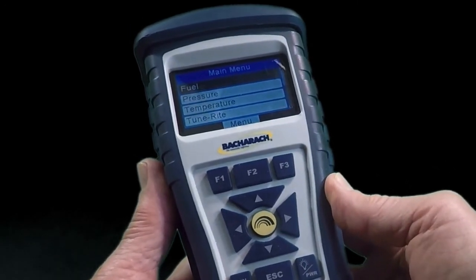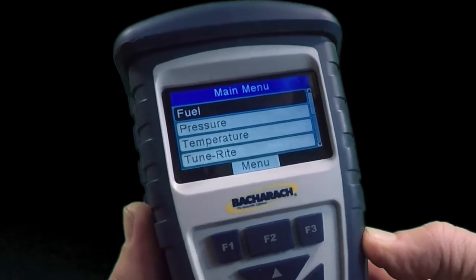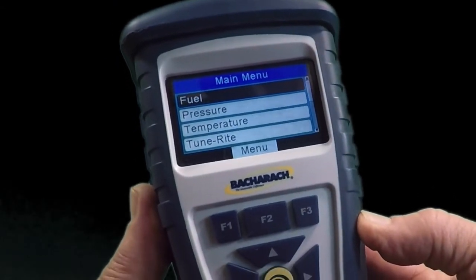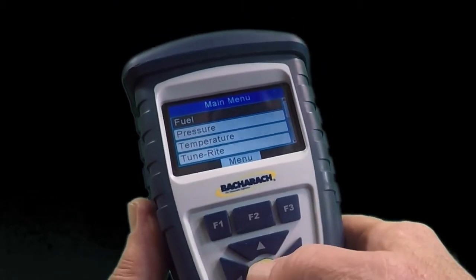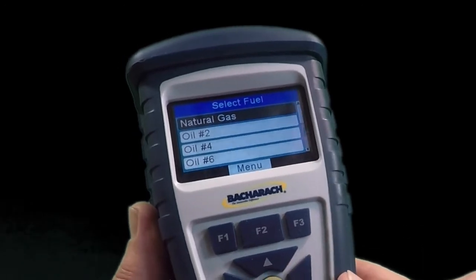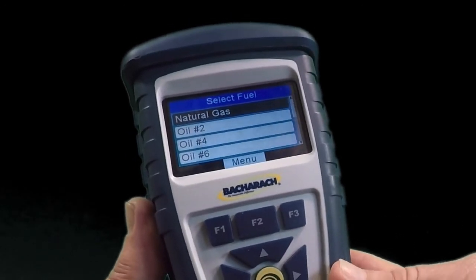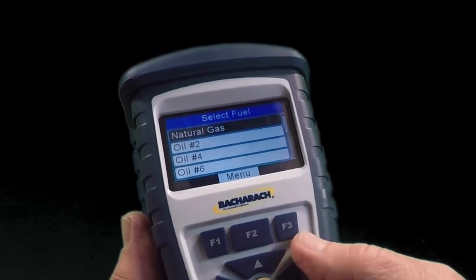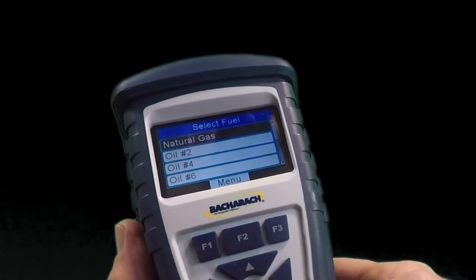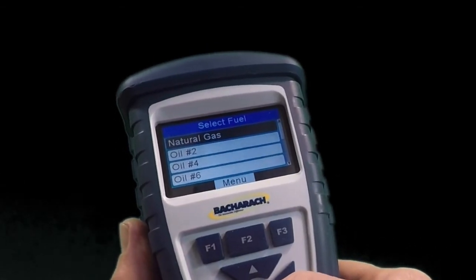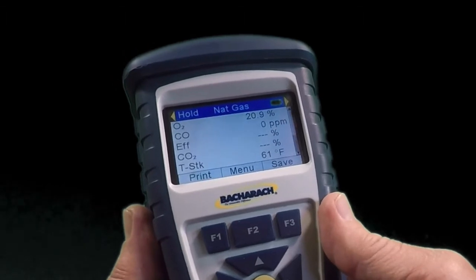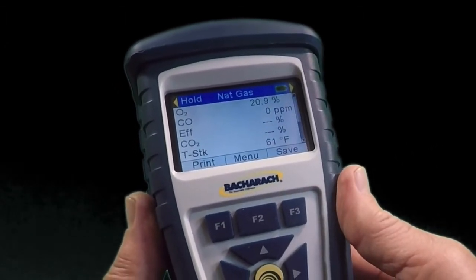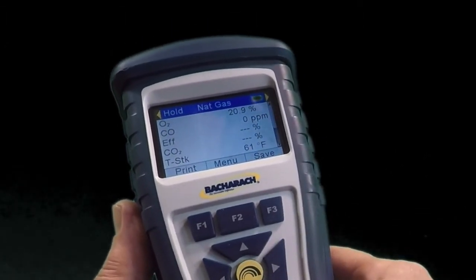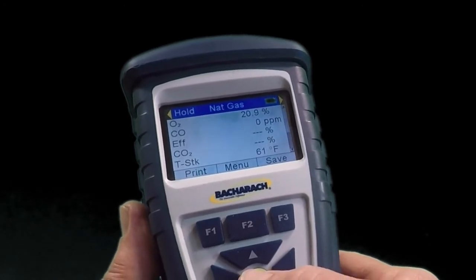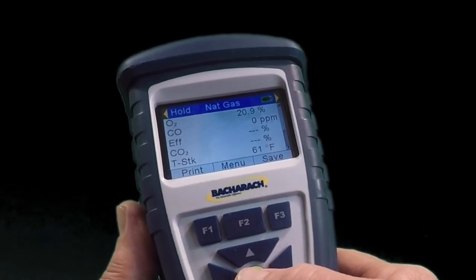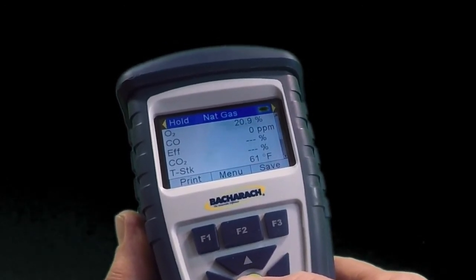To ensure that the calculated readings are correct, the first thing we want to do is enter the proper fuel type. So we'll hit the enter green button. It'll come up and say natural gas, oil number 2, 4, 6, propane, whatever. Let's say it's a natural gas installation we're on. We're going to select natural gas. Eventually, we'll have a video on how to interpret the test results and what the term calculated readings means.